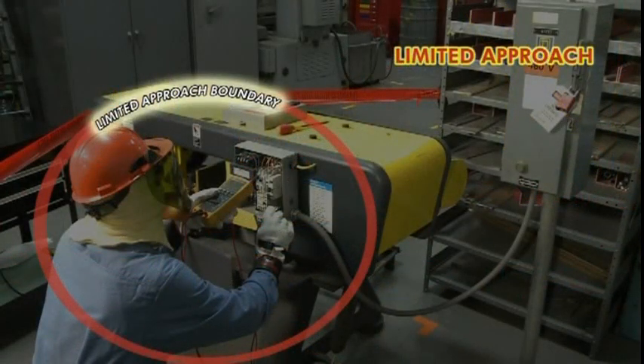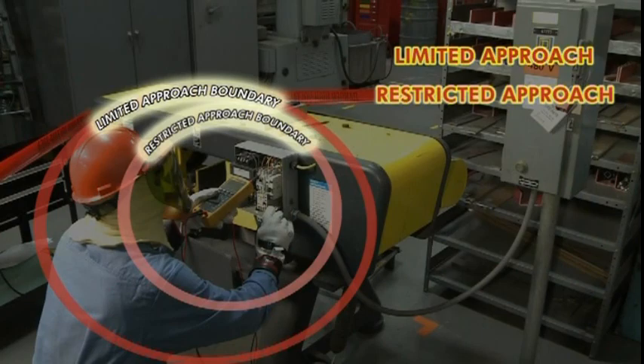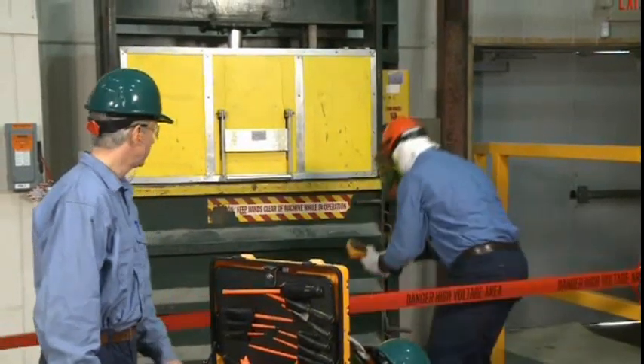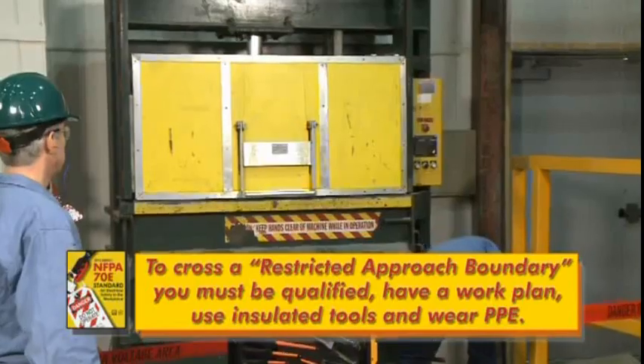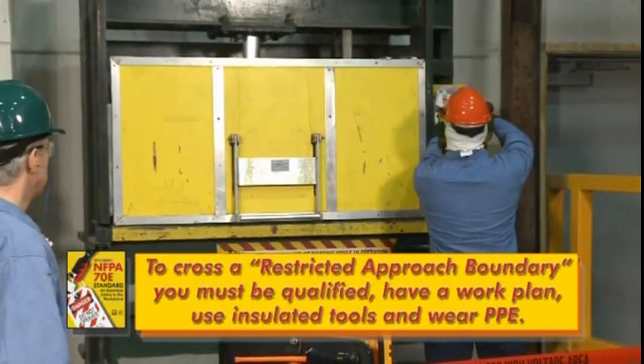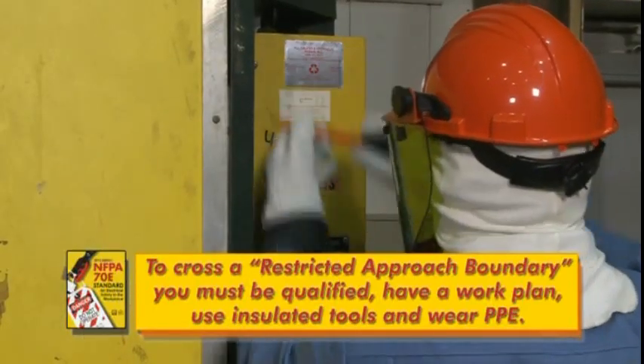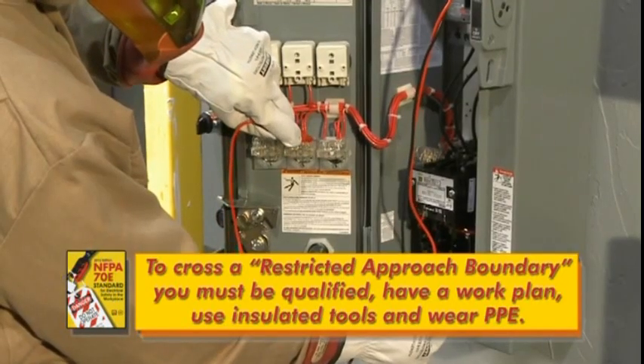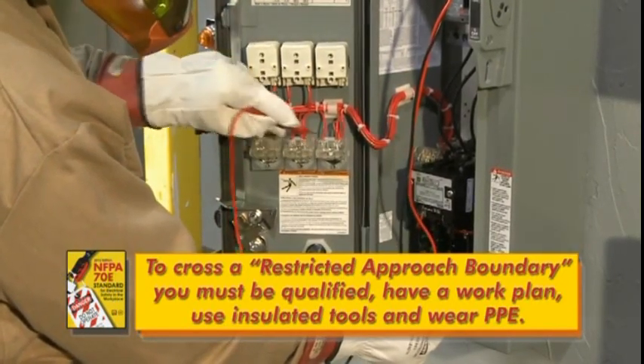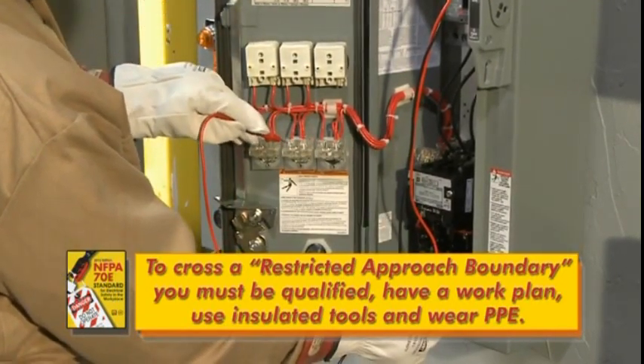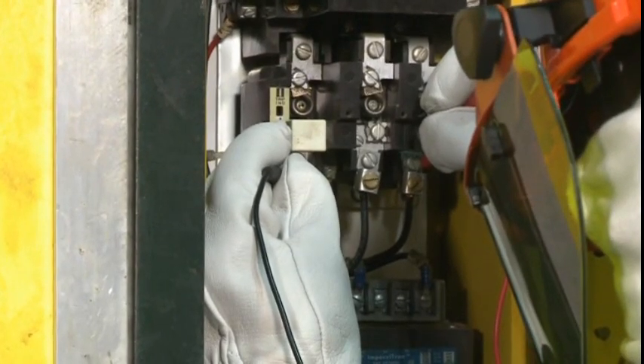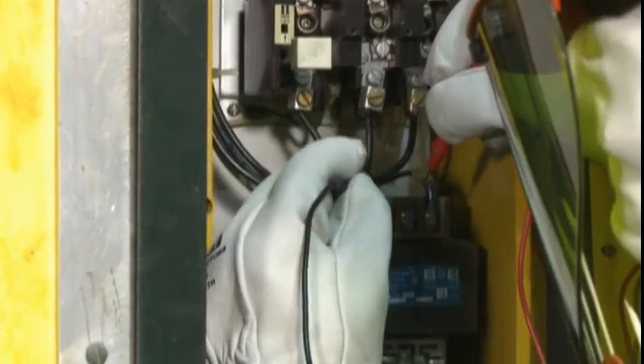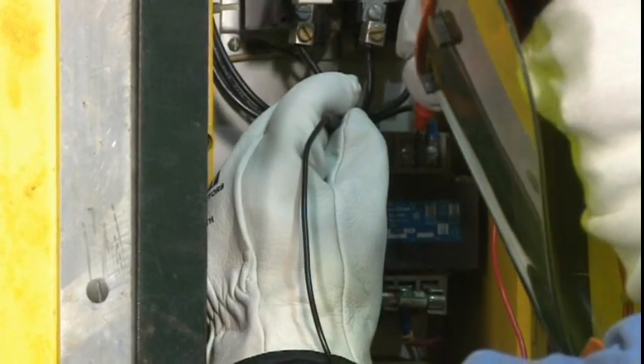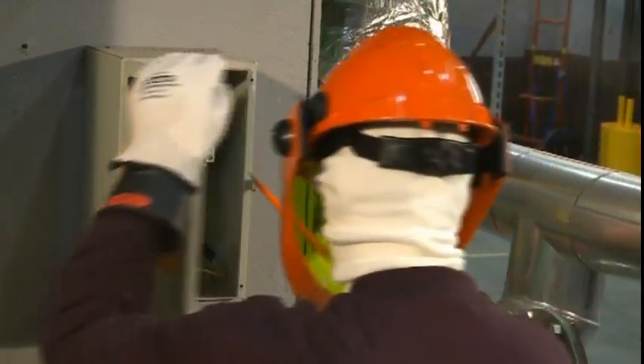The next boundary is the restricted approach boundary. Moving closer to energized parts and crossing the restricted approach boundary requires you to be a qualified person and have a work plan. You must use only insulated tools, and you must wear all required protective equipment, including rubber insulating gloves. When using rubber insulated gloves, always wear leather protectors to avoid damaging the glove and to provide thermal protection in the event of an arc flash.